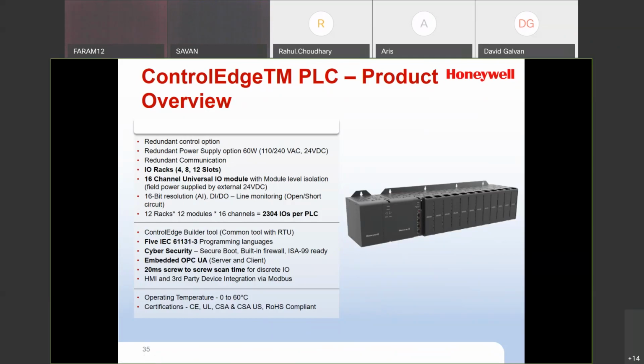So when it comes to continuity, everything is there. You have one platform, one set of tools, one training, you name it, for the PLC and for the RTU. The ControlEdge PLC also complies with IEC 61131-3, so you get all 5 programming languages. You get ladder logic, function block, sequential function chart, structured text, and instruction list. So if you're a site that likes ladder logic for whatever reason, and all your guys are trained on ladder logic, you can continue to use ladder logic.